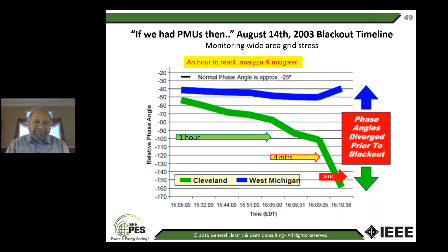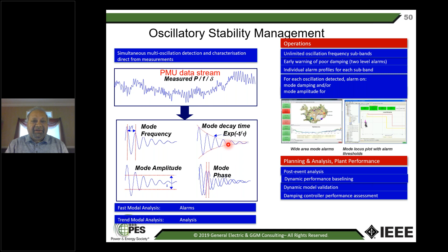Stability management is something we can do with PMUs. We can extract the frequency, the amplitude, the decay time, and the phase. All these are nice to have, but this is the critical piece of information: if most oscillations on the grid decay quickly. Disturbances occur on the grid second by second, and most are well damped and disappear. But occasionally you may have an oscillation which is not damped, meaning it increases over time. That is the one we need to look at and alert the operator, asking what can we do to avert that from continuing?